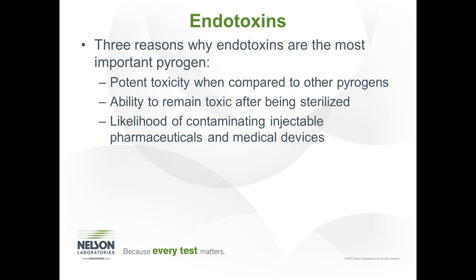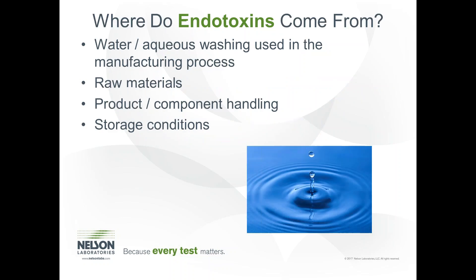The typical depyrogenation cycle is greater than 250°C for greater than 30 minutes. As you can imagine, not many medical devices can take those temperatures. The third reason that endotoxin is so important in our industry is the likelihood of contaminating pharmaceuticals and medical devices. Gram-negative bacteria are common in the environment and therefore can contribute endotoxin to these medical products.